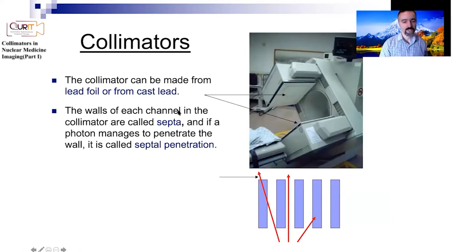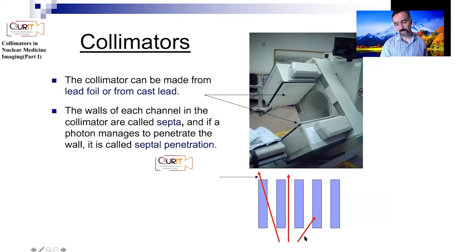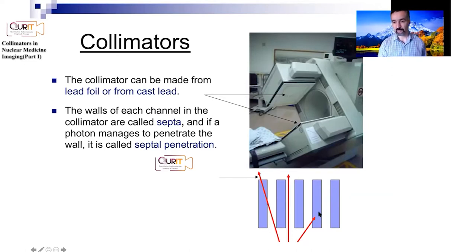These collimators are typically made from lead foils or from cast lead. The walls between the holes are called septa, and the whole collection is called a collimator. If photons manage to penetrate through the septa, we call that septal penetration, which is not supposed to happen commonly. The design should ensure that more than 95% of the time you are stopping photons from septal penetration.